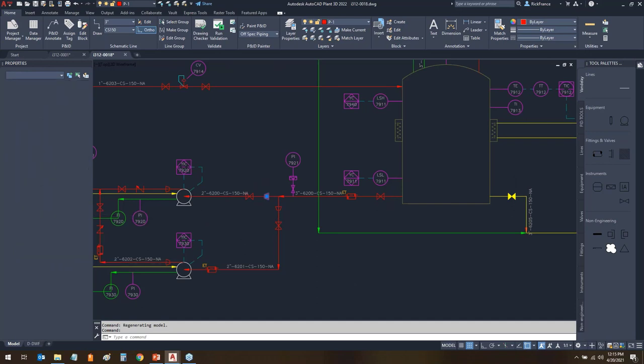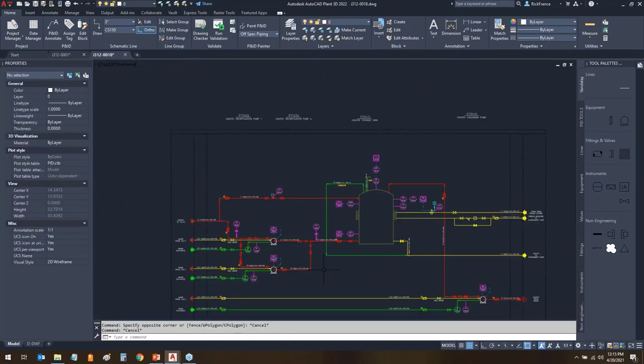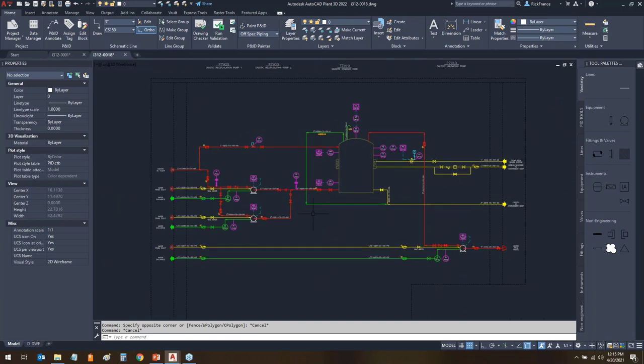So the other thing you have to be aware of scale factor wise is negative scale factors. I don't have any in this drawing, but if you mirror something, it may have a negative scale factor. Rotation can also affect how the block comes over. So you need to be aware of things like that. Most of the time with negative scale factor and rotation though, you can probably easily fix it because it'll stand out once it's converted to P&ID. But you want to prepare this stuff.